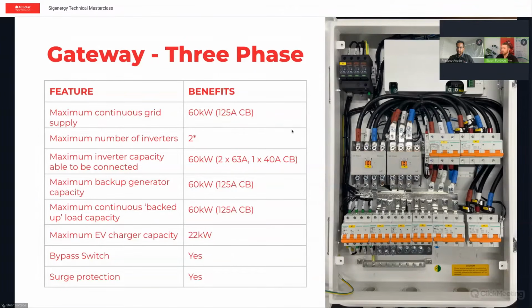An important note on this gateway is that there are 3 default incoming breakers for your inverters, but there is only a maximum of 2 inverters to be connected to this gateway. Now, they put 3 in there because there's 2 63 amp breakers and 1 40 amp breaker, and that just allows you to do different combinations, whether you want to do 2 30 kilowatts or you want to do a 30 and a 20, for example. But on the enclosure above those breakers, there is a very clear label saying only use a maximum of 2 inverters. And that's really important to take note of.